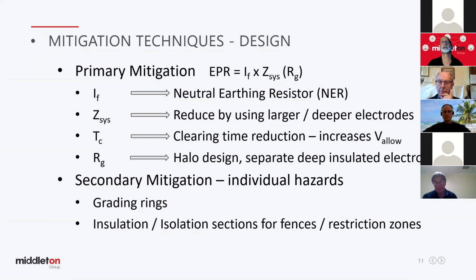So we go the other way and look to use an increase in resistance of that grid to reduce the fault current, which will increase depending on the protection. I'm not a guru on protection, but depending on the protection it can increase the clearing time and become your foe again. But basically with these designs, I've done a number of them in New South Wales, we can put, as I said earlier, a deep insulated electrode in, reducing the exposure of the electrode to the soil deep down. The less exposure, the higher the resistance will be from that electrode, which lowers the current that does dissipate if you're buried at 30 metres into the ground.